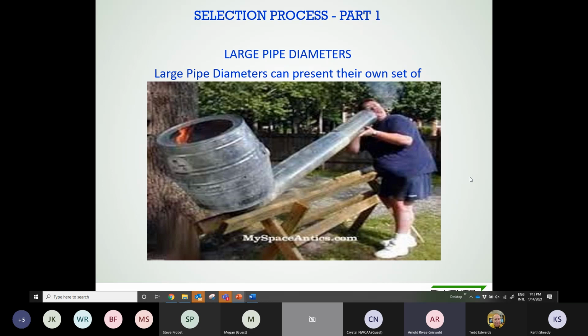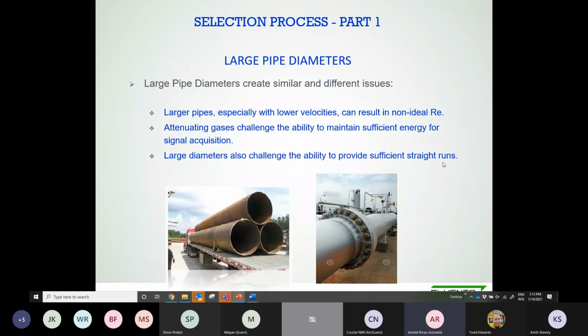So definitely large pipe diameters can represent a problem. In different situations, we have to design for the worst case scenario. So engineering companies will have to design for the worst case scenario. That means that within an emergency situation, they will have to define what kind of volume they will have, potentially what kind of gas composition they may have from different units, and then based on that, define the pipe diameter. But that's one situation that may happen, I don't know, maybe less than 1% of the operational time. But then the other 99%, you're going to be flowing very low flow or mid-range flow, and you have to have a meter that's able to handle that.